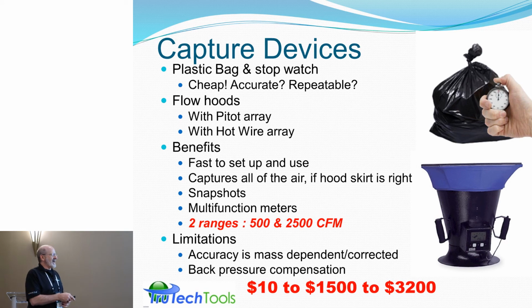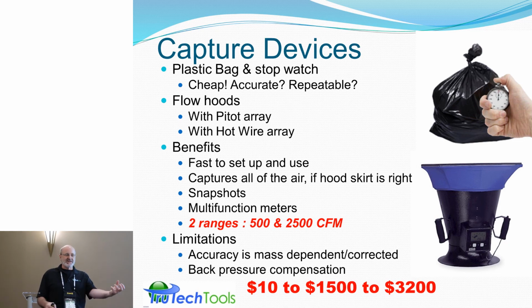Some of the limitations are mass-dependent airflow, but a lot of them have built into them, either through the meter or through actual sensors embedded in the device, corrections for air density. So the bag inflation is cheap, but the flow hoods are in the $1,500 to $3,200 range. You can't really see it here at all, darn it, but there's a grid built into the skirt of the Testo 420. Going with the flow, the idea here is it's a swirl killer, a diffuser to make more laminar flow against the flow sensor at the base of the unit. So that's a very clever, unique design upgrade.